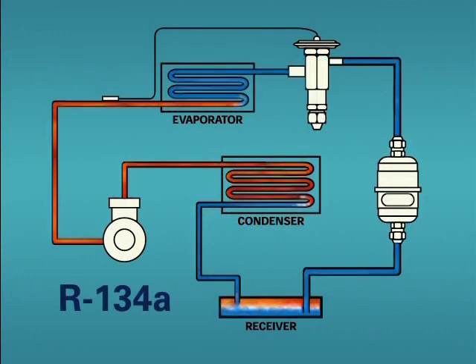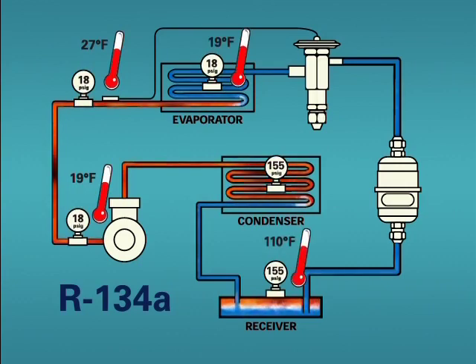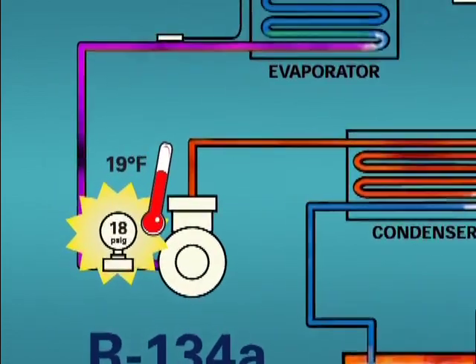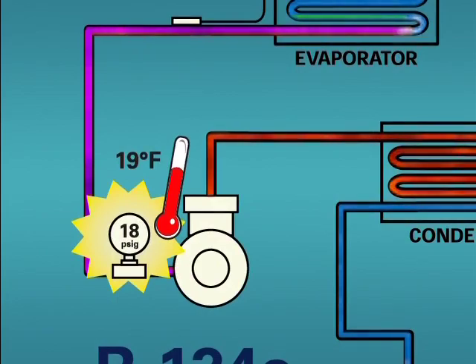Understanding the refrigerant pressure-temperature relationship in the various parts of a system will help identify and pinpoint problem areas. Because the values at the inlet of the compressor indicate a saturated condition, we know we have a problem. In this case, we have flood back because in the suction line, the refrigerant should only exist as a vapor.